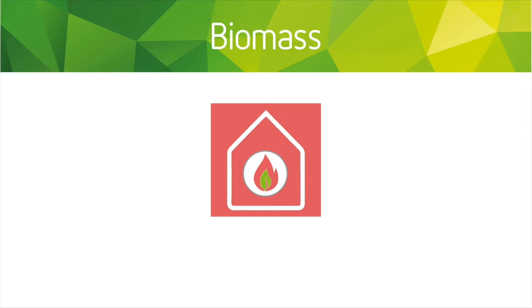With biomass, I haven't really gone through it in great detail because there are so many systems on there. You just need to make sure that the biggest problem with biomass is that you still have emissions in terms of NOx levels. So if you're bang in the city centre, it's probably not a suitable solution. You need to have fuel supplies to worry about, making sure that you get a sustainable fuel supply. You get the fuels either in wood chips or in pellets. But this is a very expensive technology, and it only really is suitable for very large homes with estates.